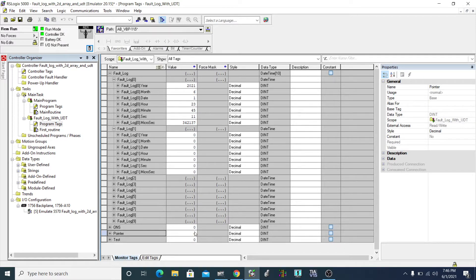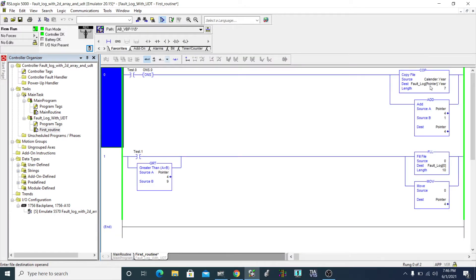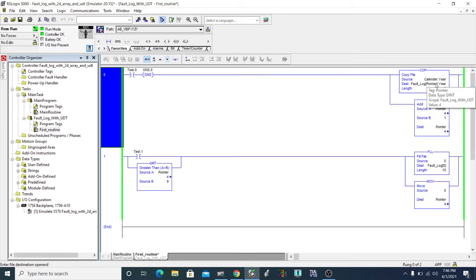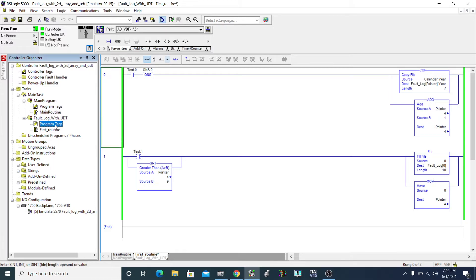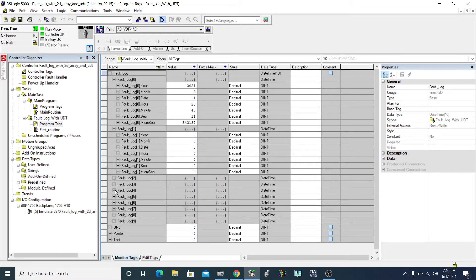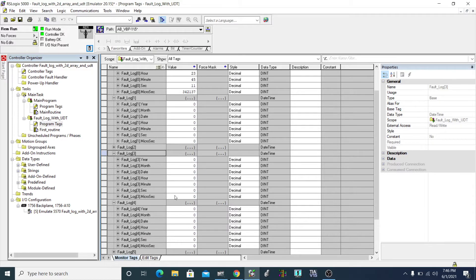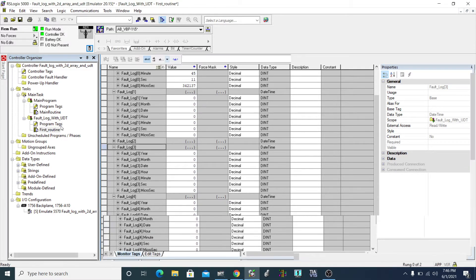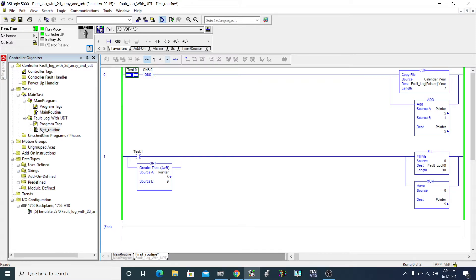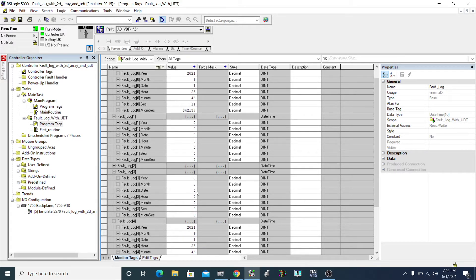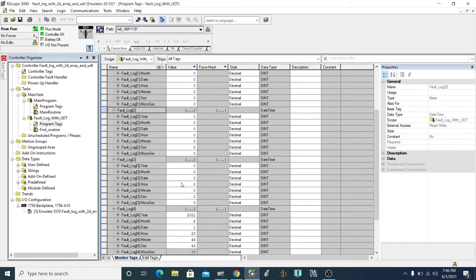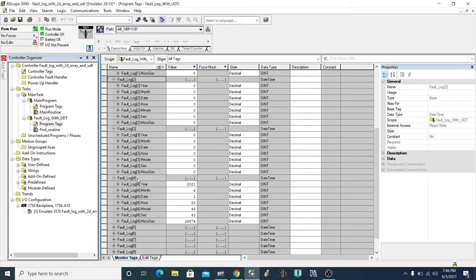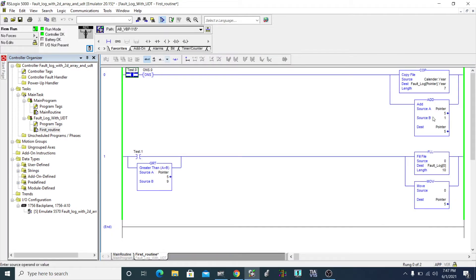Now the pointer value is four, and I'm using pointer here instead of zero. So assume it's four — this means it goes to fault log four dot here. If I execute this rung now, it will not go to zero, one, two, or three — it will go directly to four. Look at the program: it did not copy-paste to number three or number two, because pointer value was four, so we went straight to fault log four.